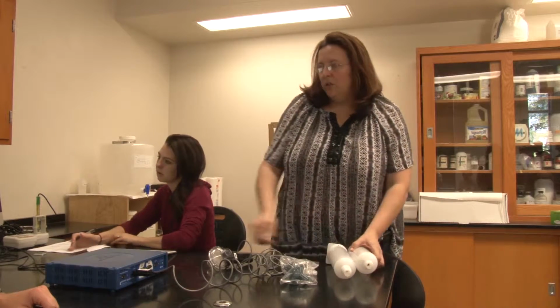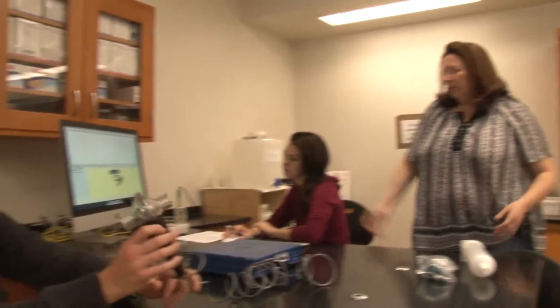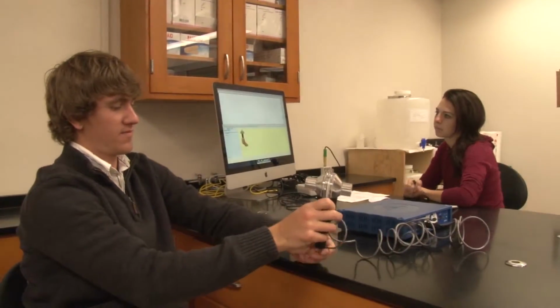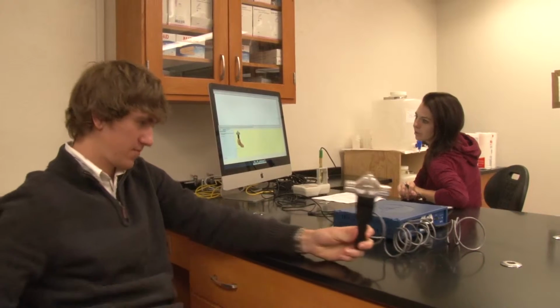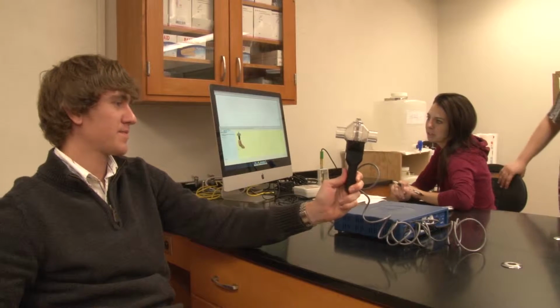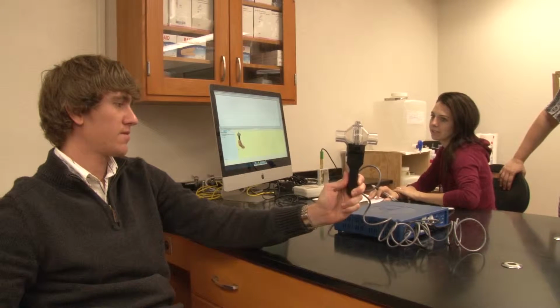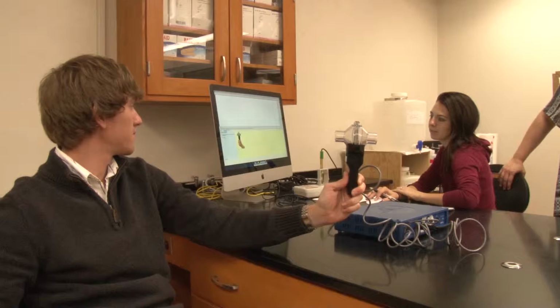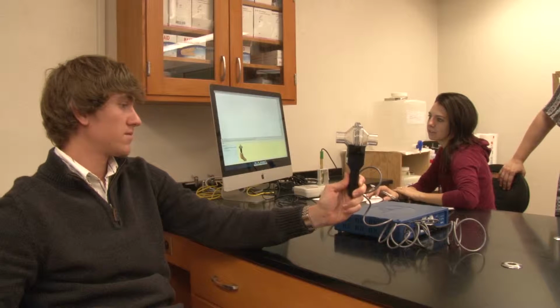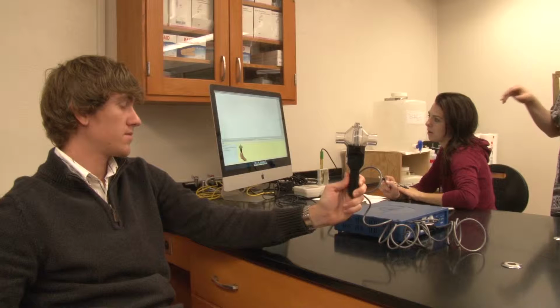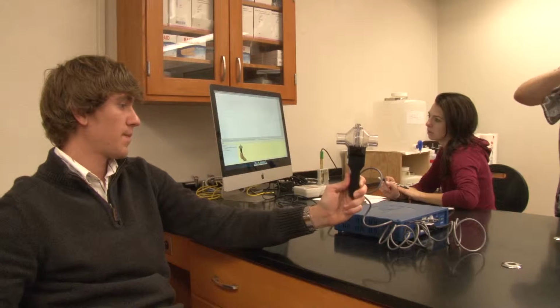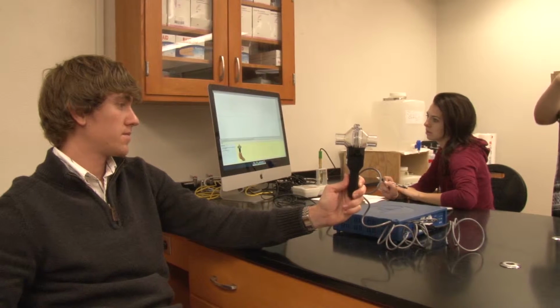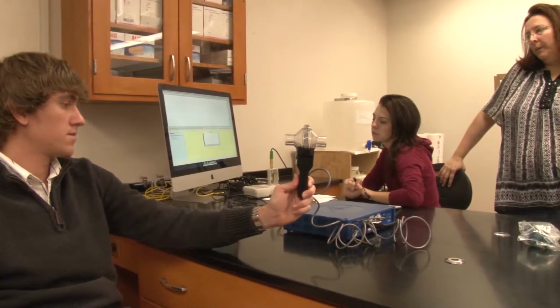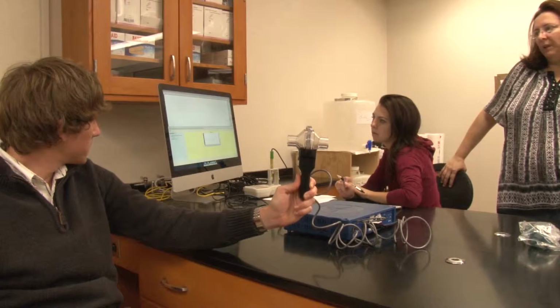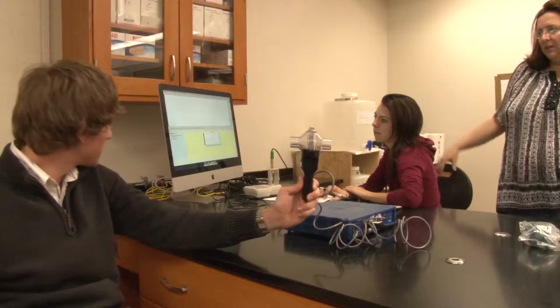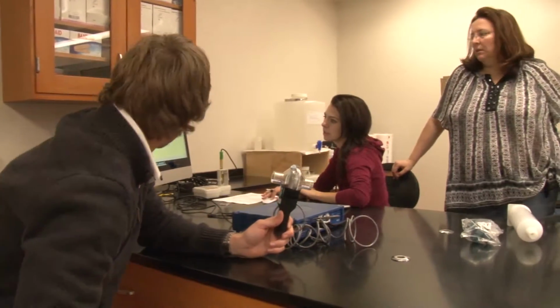So I'm going to hand you the mouthpiece. Okay, so you want to tell them what to do? Based on the screen, I'll just step back here. Hold the airflow transducer vertical and still, making sure no air is flowing through it. Okay, so the computer is going to go through 2 times and it's going to calibrate. It's important that they aren't moving this around and creating airflow within the transducer. And then you just check and make sure that it's a flat line. If it is, then you can continue. If it isn't, they need to redo it.